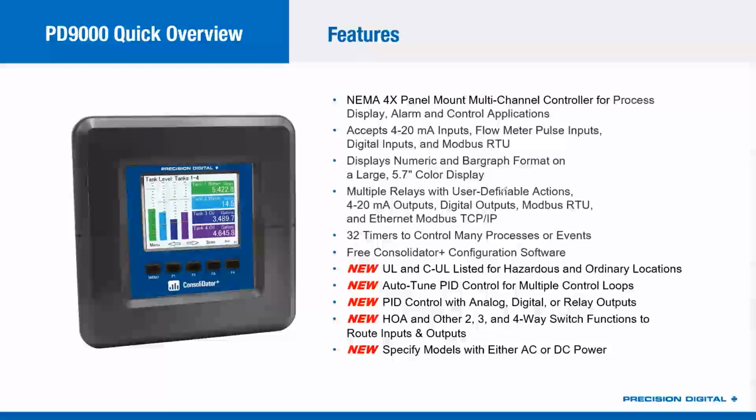With those relays, you can do all sorts of display and control, or mostly control, obviously, features. You can have alarms. You can have those alarms based on highs, lows. You can make math channels and then have those relays based on them so that you can do operations such as rate of change alarms or ratio alarms. You can do pump control with this, pump alternation. Really broad range of what you can do with these relays, some of which you've seen in our panel meters before, but much, much more than that.